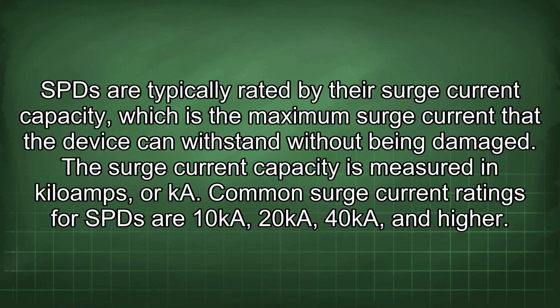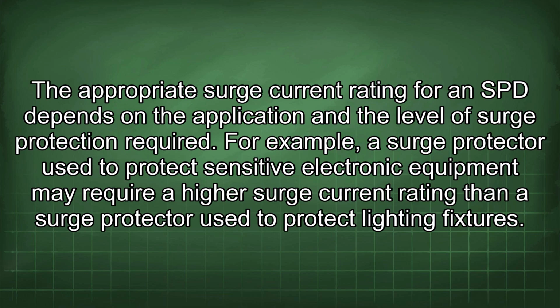SPDs are typically rated by their surge current capacity, which is the maximum surge current the device can withstand without being damaged. The surge current capacity is measured in kiloamps, or kA. Common surge current ratings for SPDs are 10 kA, 20 kA, 40 kA, and higher. The appropriate surge current rating for an SPD depends on the application and the level of surge protection required. For example, a surge protector used to protect sensitive electronic equipment may require a higher surge current rating than a surge protector used to protect lighting fixtures.